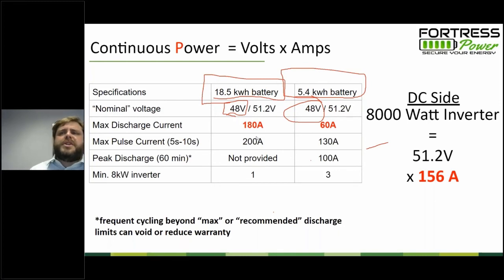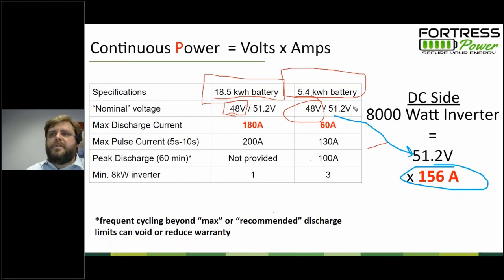if you pull open the Fortress Power spec sheets, you'll see that we list our battery nominal voltage at 51.2 volts instead of 48. And it would be conservative to do this, 8,000 watts divided by 48, and that would give you an even higher DC side amperage. But more accurately, perhaps a little bit less conservative, you use the nominal voltage. A little bit higher voltage will give you a little bit lower amperage if you need to shave an amp or two out for your wire size calculations. And what that is saying is that the lithium ion batteries, or at least our lithium ion batteries, the bottom of their voltage range is going to be about 51.2 volts or so. Any resting voltage that's lower than that, you're getting down to the bottom of your depth of discharge.